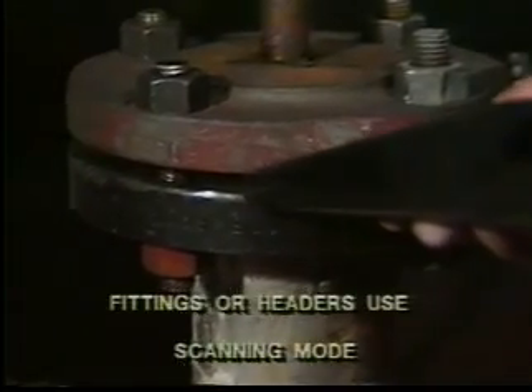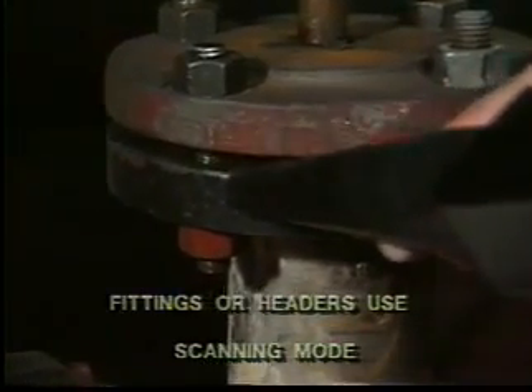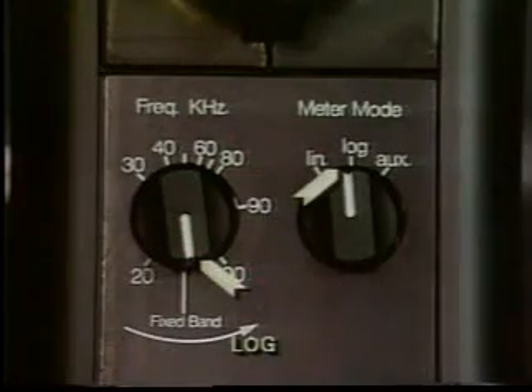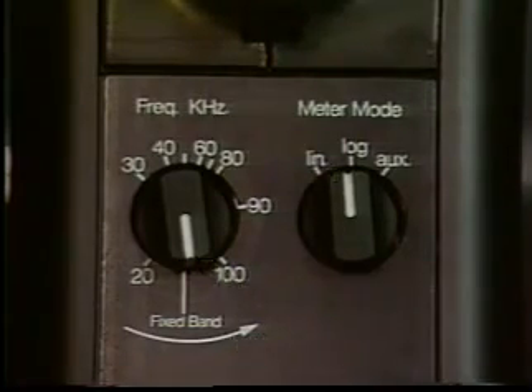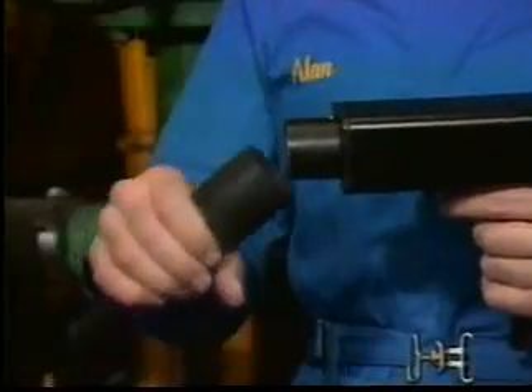To locate a leak in fittings or headers, use the scanning mode. With the ultra probe scanning module in the fixed band position and set at log, scan a general obvious area. Adjust the sensitivity on the ultra probe to focus in on the loudest point, moving from gross to fine sounds, or closer and closer to the leak site. You may need to use the rubber probe. Confirm the leak by moving back and forth across the site. Check all the fittings as well as the headers. The scanning method is explained in full detail in UE Systems' leak detection training videotape.